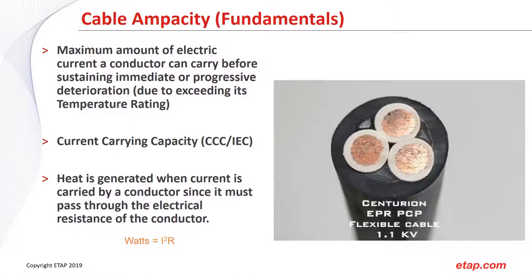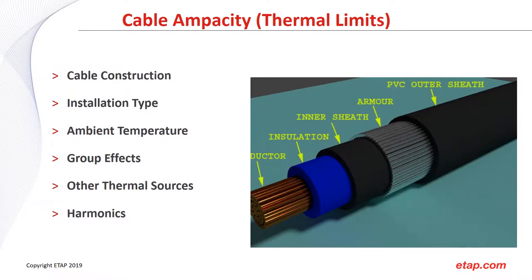Another term for this is current carrying capacity, or CCC, which is how it's commonly known in the IEC world — anywhere using 50 Hz systems. Heat is generated when current is carried by a conductor, since it must pass through an electrical resistance — in this case, copper. The equation is Power (watts) = I²R. For cable ampacity, it's also very important to consider thermal limits, which include all layers of the cable construction from the outer PVC sheath down to the conductor, including the insulation, inner sheath, and armor.